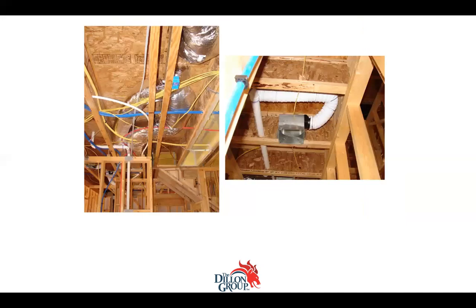And again, more of the same. But this time I got a good picture of the exhaust fan in the bathroom, because the exhaust fan was installed by the electricians and the ducts are run by the HVAC guys. So the electrician doesn't care which way the exhaust port points, and the HVAC guy doesn't bother to flip it around. He just does this. How much air do you think is going to get exhausted out of that exhaust fan? A solid 6 to 8 CFM. Yeah, that's about what we see.